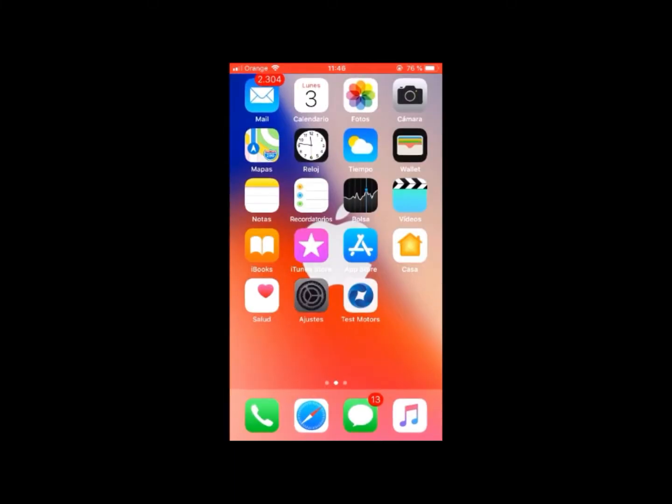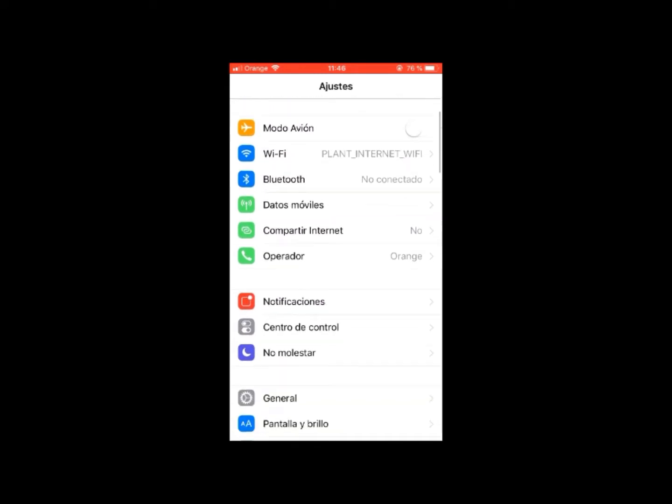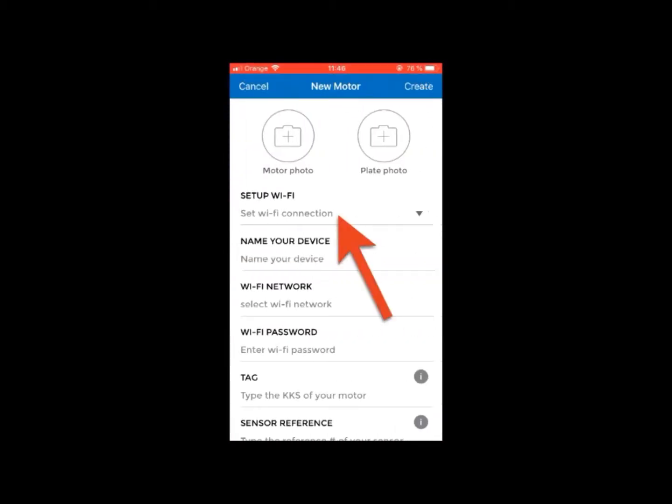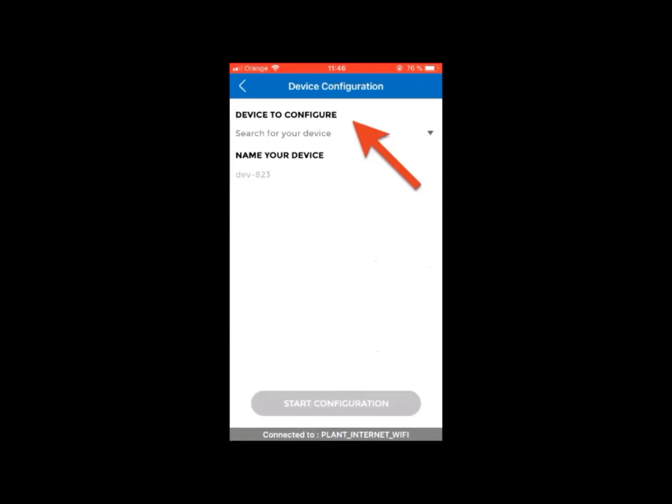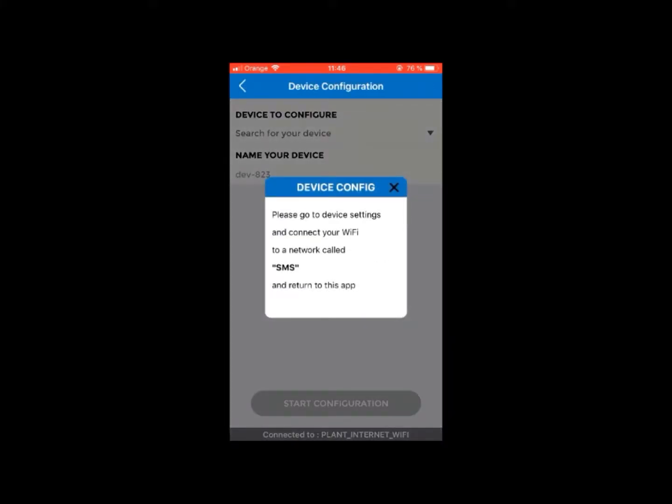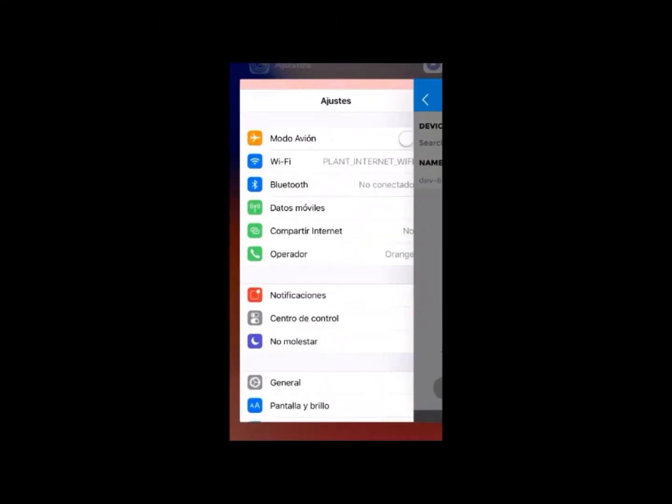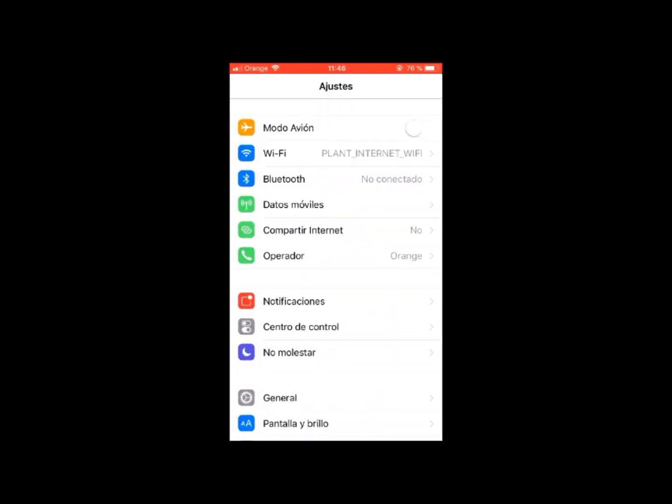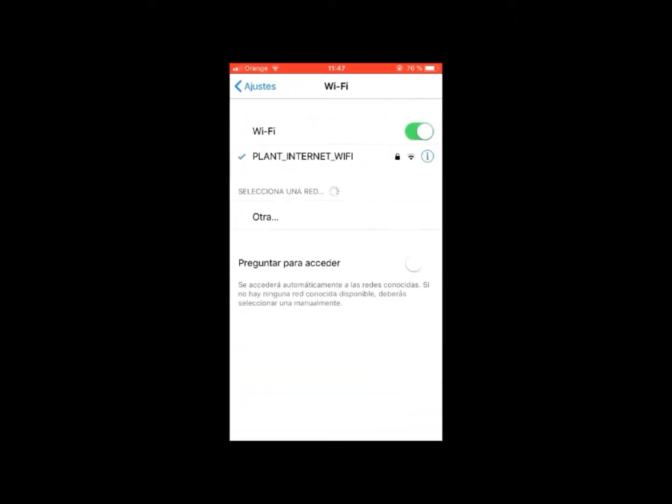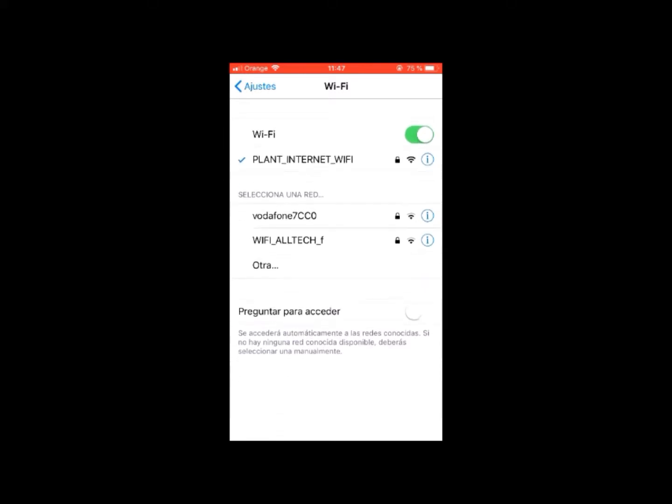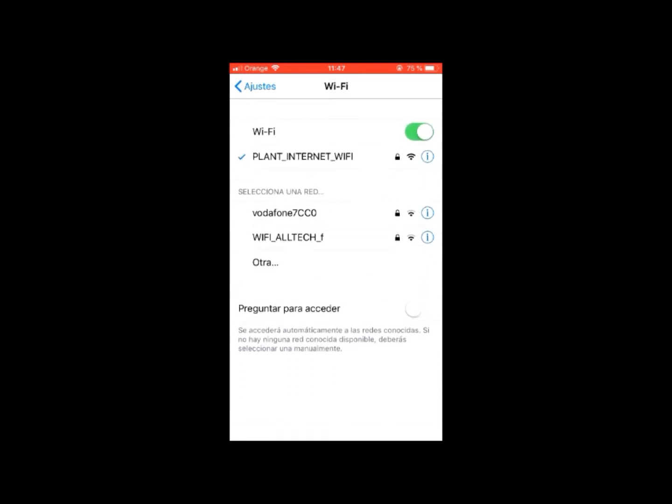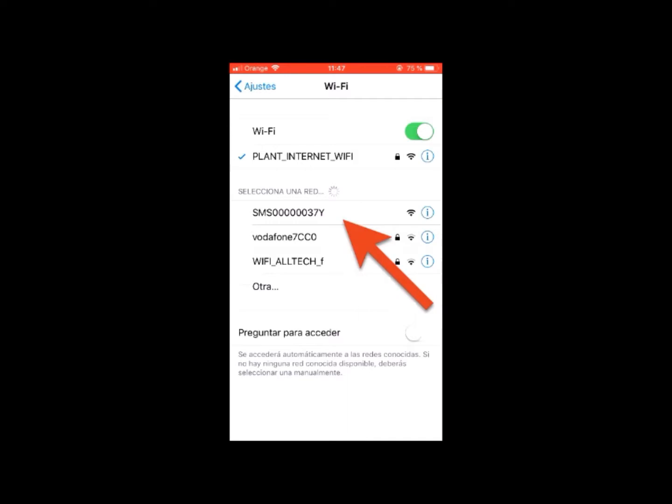Before adding a new motor, connect your mobile phone to the Wi-Fi network available in the plant or to the Wi-Fi router provided by TestMotors. You can return to the application now and add the motor by clicking on Add motor. Then, click on Setup Wi-Fi and click again on Device to configure. At this point, a message will appear requesting that you exit the application and search on your mobile settings for the Wi-Fi network generated by the sensor.